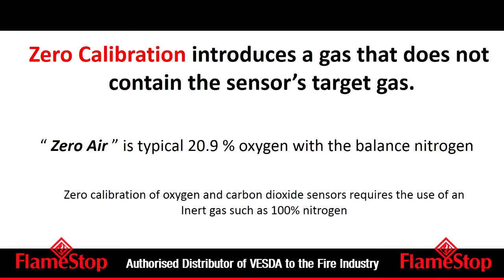Zero calibration introduces a gas that does not contain the sensor's target gas. It is used to give the sensor a clean atmosphere reference point. Zero air is typically 20.9% oxygen with a balanced nitrogen. Zero calibration of oxygen and carbon dioxide sensors requires the use of an inert gas such as 100% nitrogen.